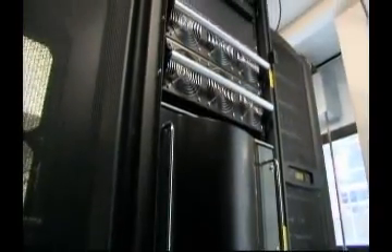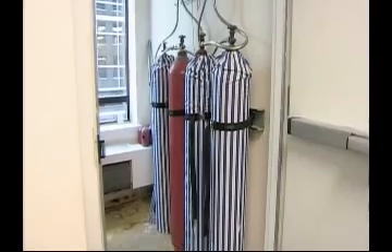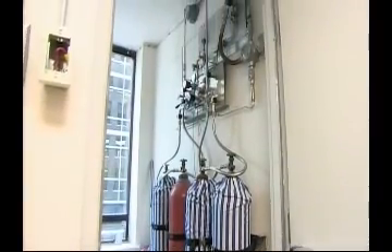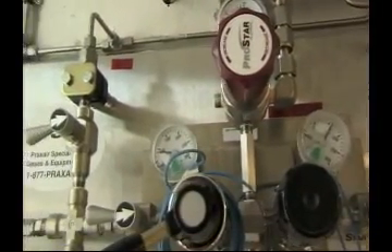If the power goes out and we didn't have the extended rack here, we'd get about two hours of backup time. You can add more batteries, but batteries take up a lot of space as well as weight. The nice thing about a fuel cell is floor space is minimal and weight is significantly less. Your storage is just your hydrogen outside your server room, and your backup is fully limited by your fuel — so if you keep the fuel replenished, your backup is continuous.